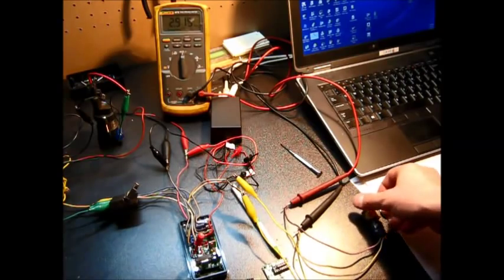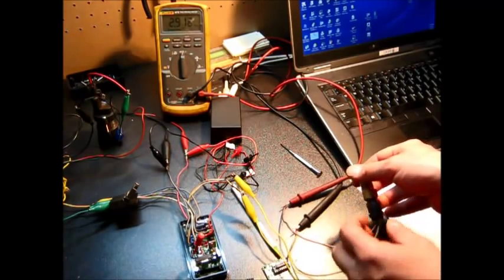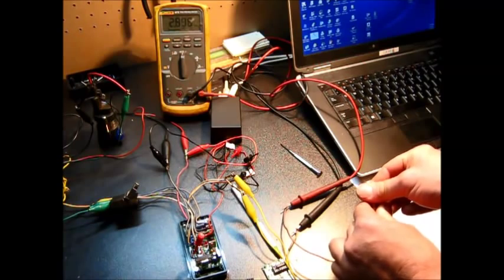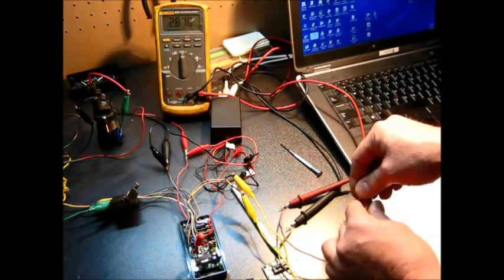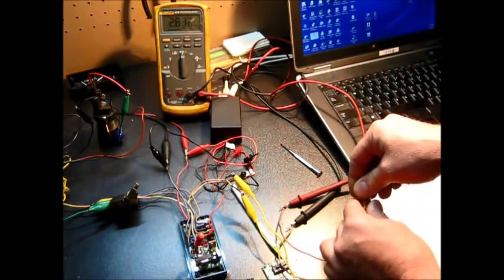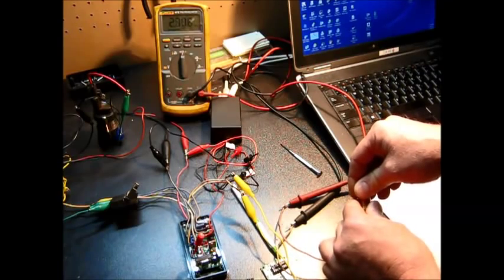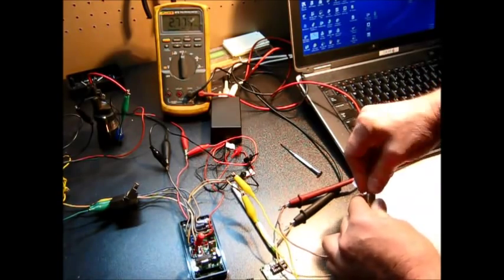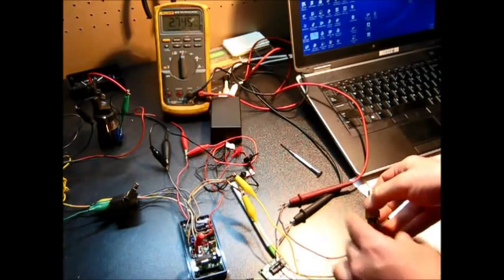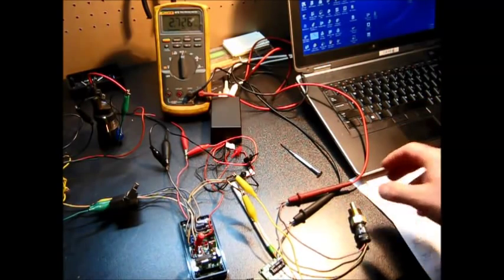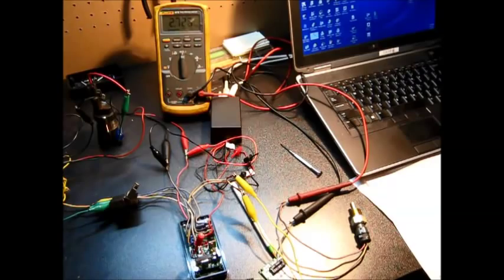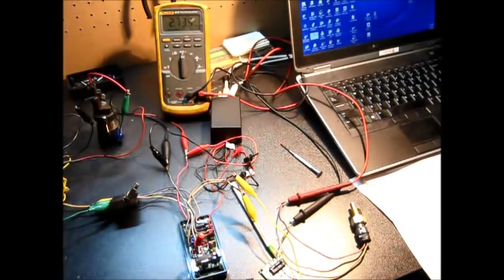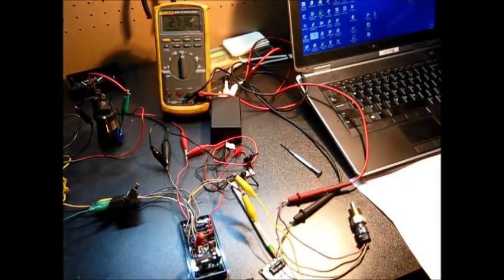2.9K ohms. Now, you see that temperature, the resistance is dropping. All I'm doing is just touching it, warming it up. And it's got a very precise temperature to resistance chart. It's provided by the manufacturer. And based on that chart, we can set the set points where the fan and the lights and the things are going to turn on and off.